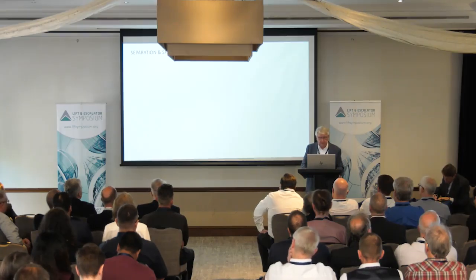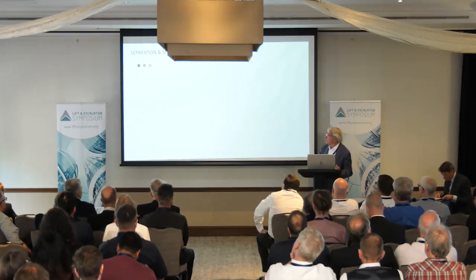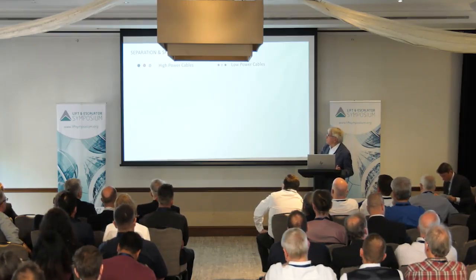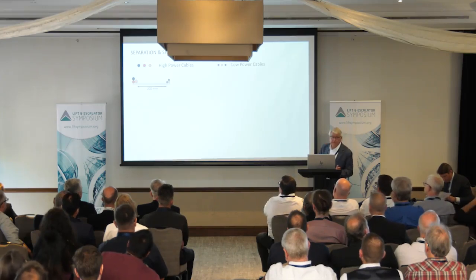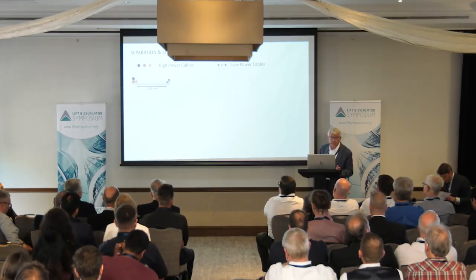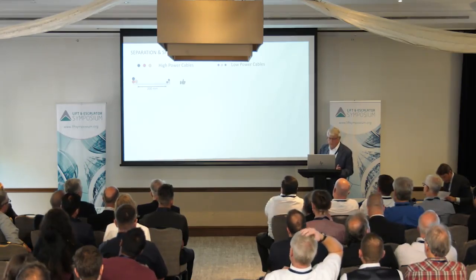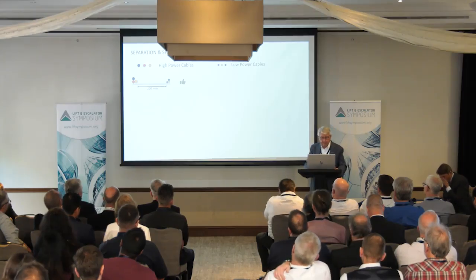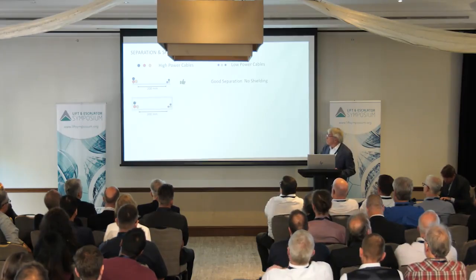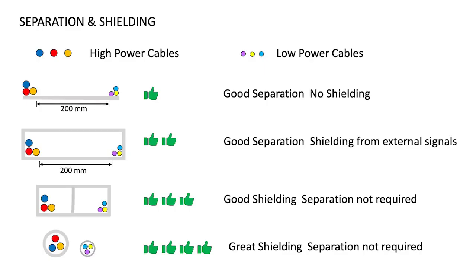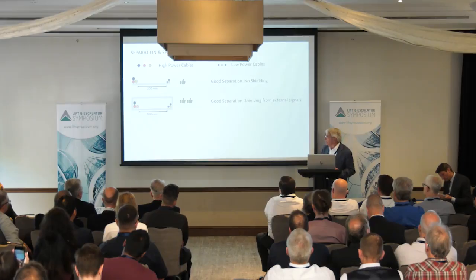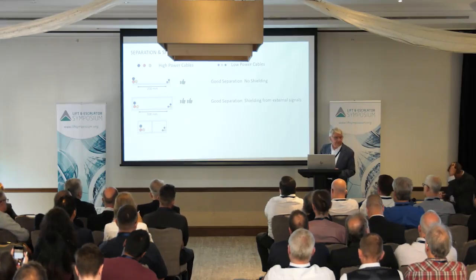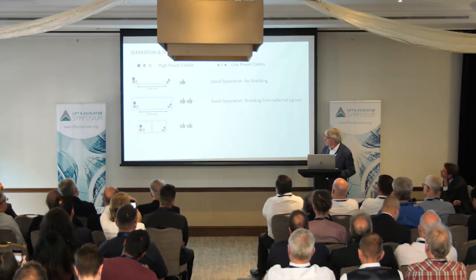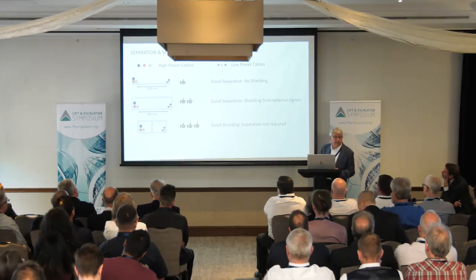Let's look at shielding and separation and which works better. Here we have high power cables and low power cables, and if we keep them 200 millimeters apart, we reduce the coupling - that's a good approach. A better approach is to put them in shielded troughing, which gives good separation while keeping outside noise from coming in. But there's an even better solution: troughing with a divider in the middle, giving you both shielding and separation, so good shielding that separation really isn't required because it's already there. Using two shielded cables also works extremely well, and that's what most people do in the real world.